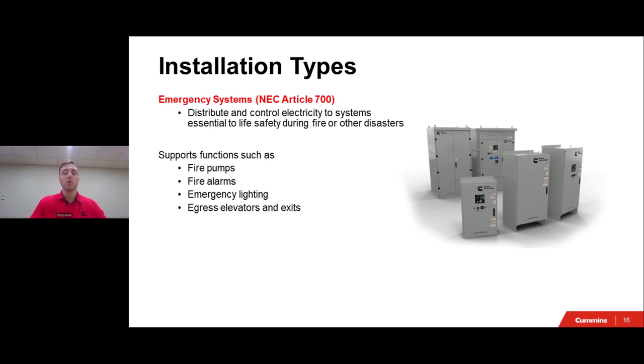Transfer from the normal power source to the emergency power source must be completed within 10 seconds and meet the requirements of Article 700 of the National Electric Code, otherwise known as NFPA 70, in addition to overcurrent protection devices being selectively coordinated with all supply side overcurrent protection devices. So if more information is needed about an emergency system and what it means, please take a look at NEC Article 700. You can find more details as to what is needed of your system and your automatic transfer switch as well.